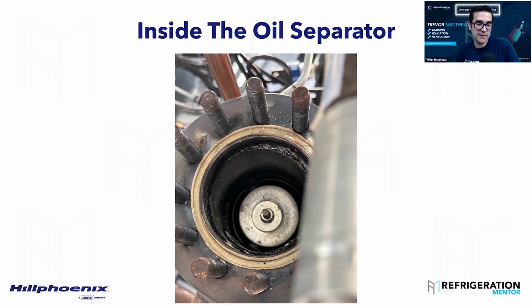And then it's all the other checks, like all the case controllers, temperatures, pressures, that they're all wired and landed correctly, overriding different solenoids, and just making sure it all works. And this is a process. You've got to make your own checklist. Yep, but the big thing is that the manufacturers supply the checklists for you. They might not say, okay, there's 1,200 pressure transducers on the site, go check them. They say check all the pressure transducers. So that's your responsibility as a technician.